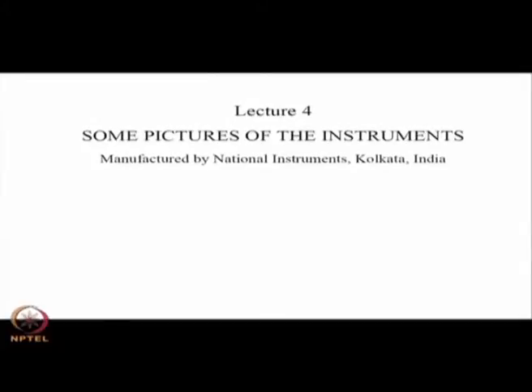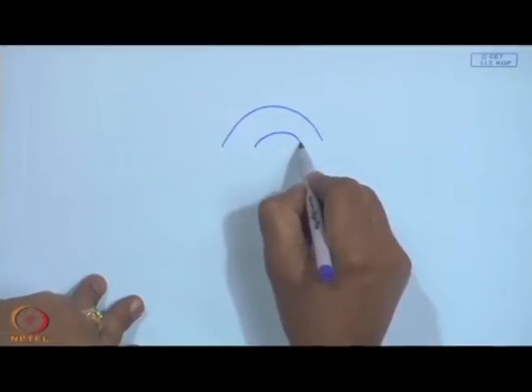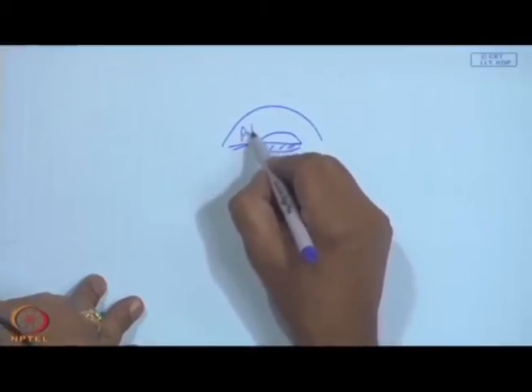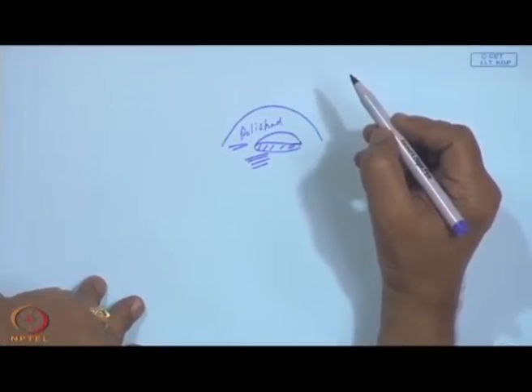I shall show you some pictures of the instruments so you will have a better idea of how they work. The cross-section details cannot be shown because the instruments are working and could not be broken. These are manufactured by National Instruments in Calcutta, India, though I believe the company is no longer working. First, you will see a pyranometer: you can see the glass bowl in the middle, with two concentric hemispheres, with Parsons black at the middle. There is a thermopile — basically thermocouples in series — which produces a millivolt output for a given radiation input.